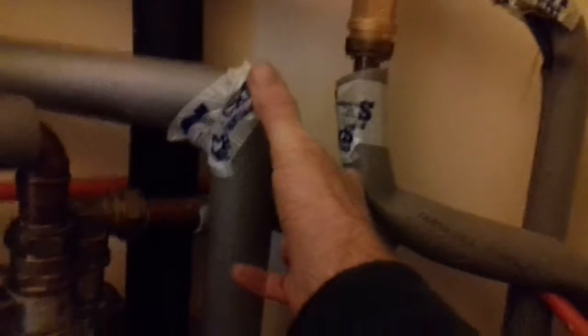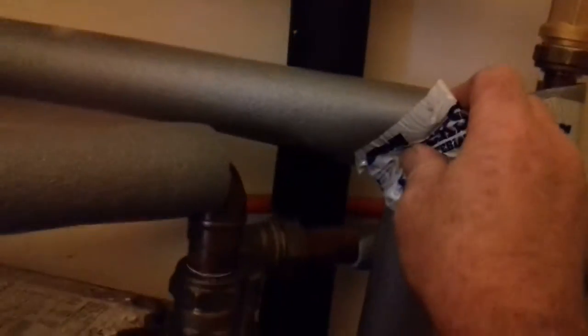So that's one side of the plate heat exchanger, but there's no pump on it. So we need to get that pump fitted. And they can fit it, I guess, on the return. It's probably better. And it would be a good idea also to put an air vent at these points here on both the flow and return, so that when you're filling it and venting it, it's easier. If we look at the flow, put an air vent there on that corner, and here on the return, maybe put another air vent or a valve vent, if the air vents don't take the temperature, and the pump, and that's that side of things.